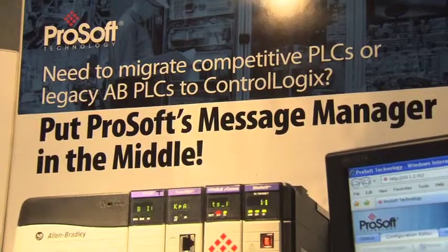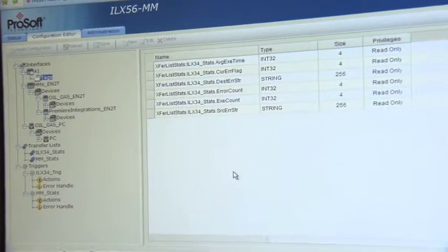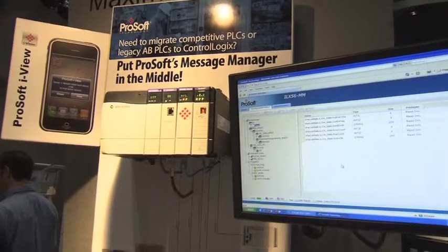The Message Manager, configured in the Internet Explorer browser, is set up with a graphical, easy-to-use environment where you add devices on a network and the backplane — whichever PLCs you have out there. You are able to browse the tags if it's an Allen Bradley PLC, point to the specific tags you want, having a source and destination, all graphically, very easy to find. You can then transfer that information based on triggers. Those triggers can be based on a time event — every second, every half second — or on events that look at other tag values in the PLC. A tag reaches a certain value, a tag turns on, and then those messages are triggered accordingly.